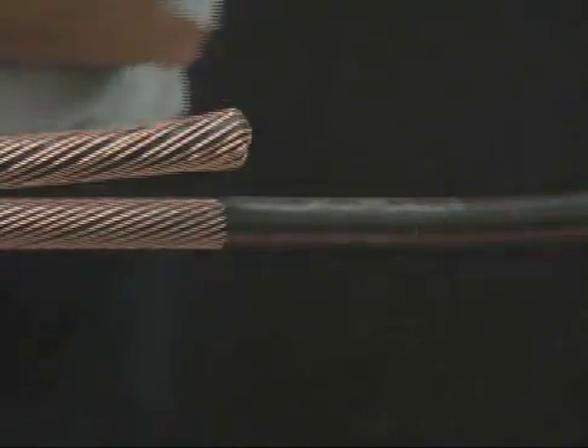Abrade the cables 6 inches back from the jacket cutback. Using an approved solvent, clean the cable jacket for 30 inches on the side where the splice body will be placed.